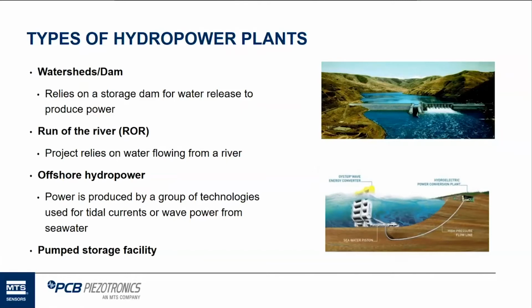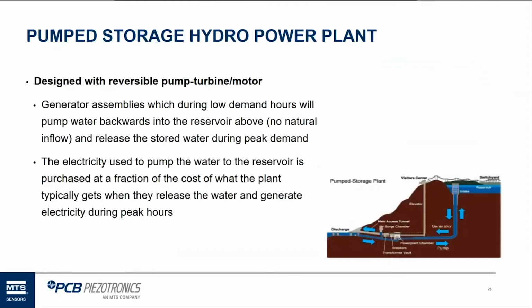There are also what we call pump storage facilities, and these pump storage hydro plants are designed with reversible turbines, pumps and motors that they can turn backwards. So, during off-peak hours, they start up the turbine and power it to fill up a reservoir at the top of the dam. So they spin it backwards and fill up the reservoir. Then they turn everything off. And when peak demand comes up and they're needed to run, they're ready. They start to release the water, and it flows back through like a regular hydro plant, and water is released and generates electricity.